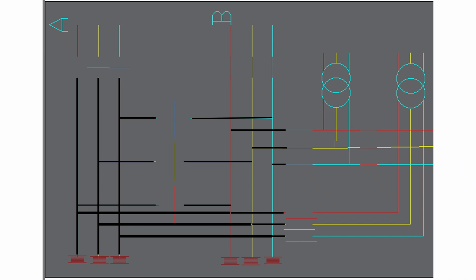Simply keep the first isolator on the transformer side switched on and don't close the isolator between the two transformers. Then the power supply of B will feed one transformer. Next, you charge the A feed, the A side isolator, so that the power supply will go to the second transformer. Now what will you do? You will change over the power supply from B to A. How?